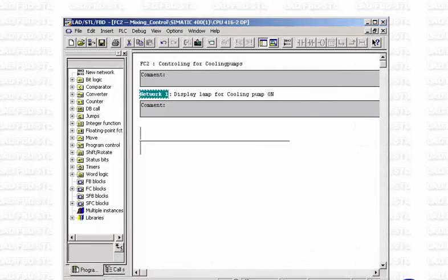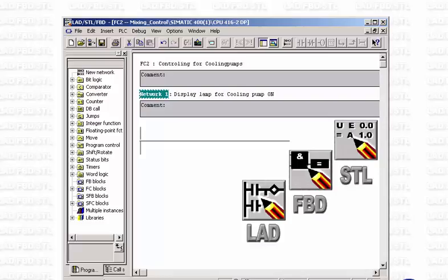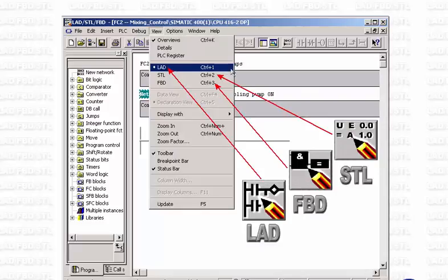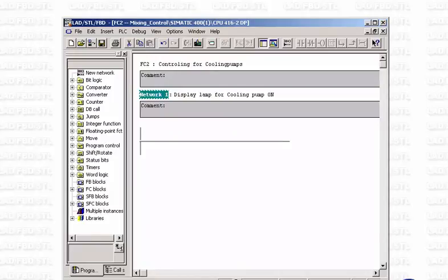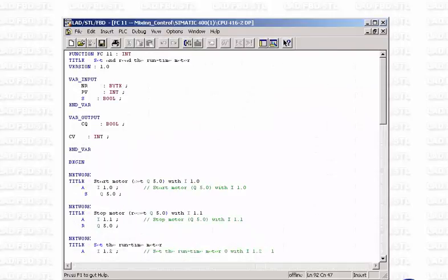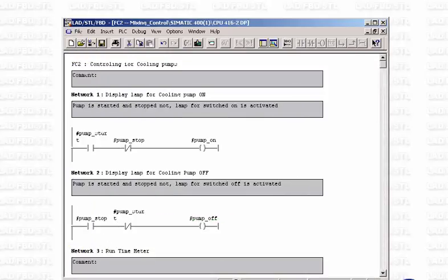Another essential element for handling your automation tasks, in addition to the function range of the three languages, is the program editor, which you use for actually developing your program. Since one and the same program editor is used for LADDER, FBD, and STL, you can generate your program block by block and specify the programming language individually for each block as required. The program editor lets you choose between two types of programming. With source-oriented programming, you write a program source which is then compiled into the executable program code. With incremental programming, the program is immediately checked and compiled as it is entered, so that only syntactically correct blocks are created.